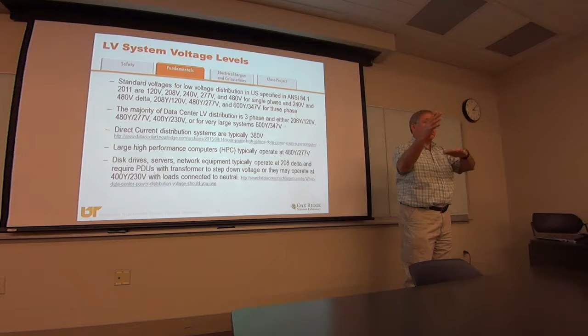And I found a website where they're basically taking 480 volt and converting it down to DC and putting batteries in the cabinet. So basically they've got a backup in the cabinet, and they're busing 48 volts. And they're getting a lot of efficiency gains because they get rid of all the conversions up and down from AC to DC.